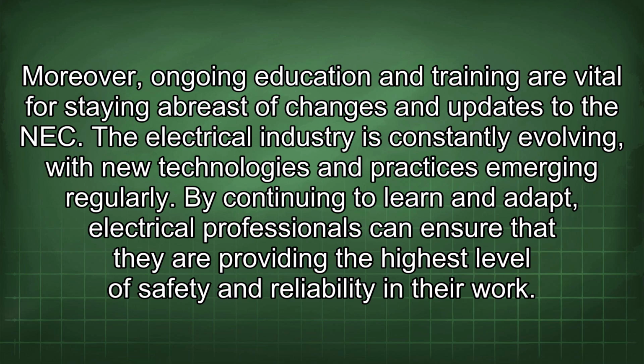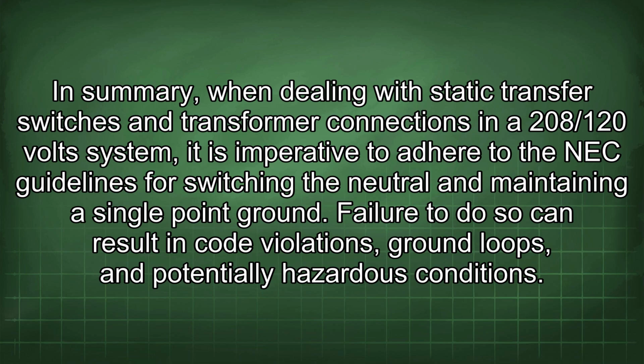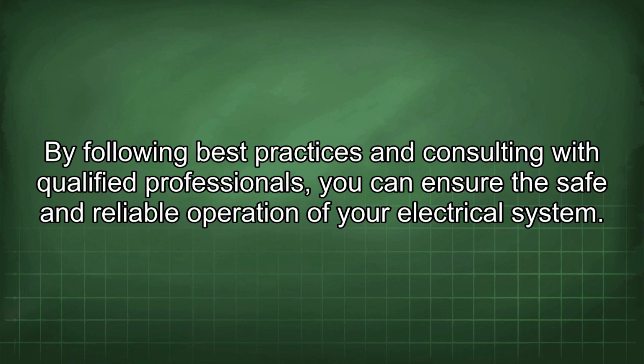In summary, when dealing with static transfer switches and transformer connections in a 208/120 volt system, it is imperative to adhere to the NEC guidelines for switching the neutral and maintaining a single point ground. Failure to do so can result in code violations, ground loops, and potentially hazardous conditions. By following best practices and consulting with qualified professionals, you can ensure the safe and reliable operation of your electrical system.